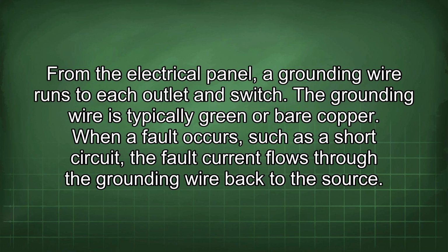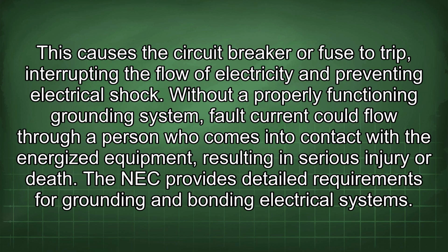When a fault occurs, such as a short circuit, the fault current flows through the grounding wire back to the source. This causes the circuit breaker or fuse to trip, interrupting the flow of electricity and preventing electrical shock. Without a properly functioning grounding system, fault current could flow through a person who comes into contact with the energized equipment, resulting in serious injury or death.